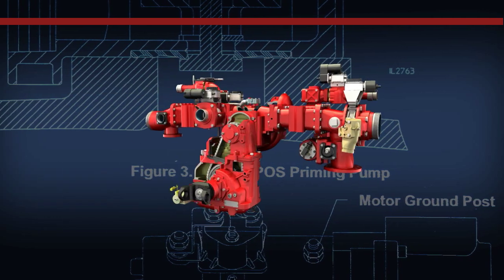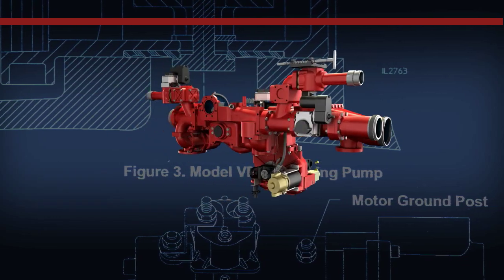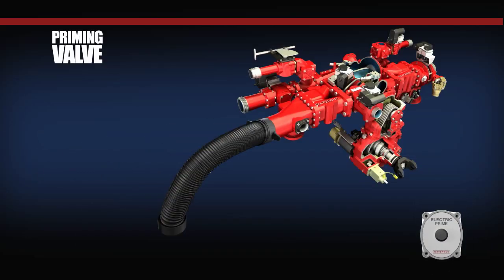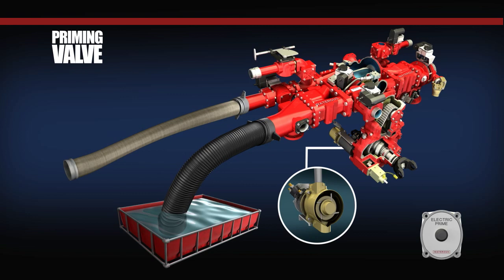The Waterous priming system consists of three main operating components. The first is the priming switch, located at the pump operator's panel. The priming switch utilizes a weatherproof switch and wiring connections, and when the button of the priming switch is pressed, the electrical circuit is completed and current flows through the switch and into the solenoid on the priming motor.